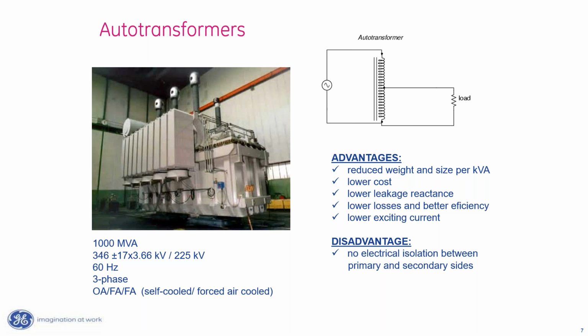And I mentioned that it doesn't have to be like what I think of it, because you also find these auto transformers in things like voltage regulators out on the distribution system, a lot of different things. The other place that we find transformers, I said there was a fourth location, is inside of industrial facilities. As we get down into the industrial facility, we might step down from medium voltage, from 4 kV down to 120 V, that sort of thing. Now, when we get down to that level, typically we don't have transformer differential. Usually when we're talking about transformer differential, which we'll spend most of our time on today, we're talking about one of these first three types that I mentioned, these bigger, larger transformers.